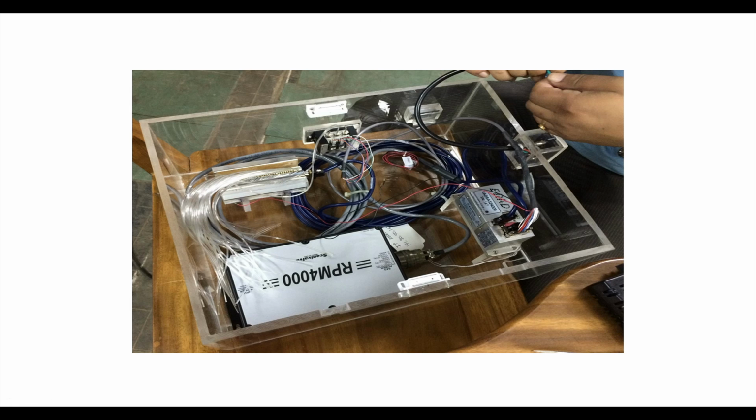Yeah, it is required because if you provide a certain pressure from these 3 units to those 3 ports available on the scanner with a certain logic, that logic is provided along with the scanner unit, then it is going to operate in a certain mode. It may be a calibration mode, it may be a data acquisition mode.